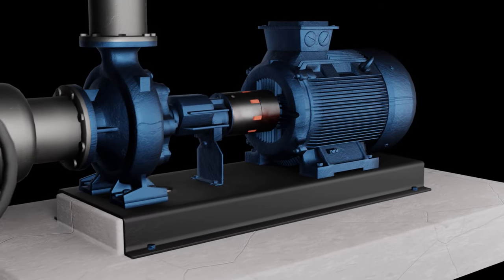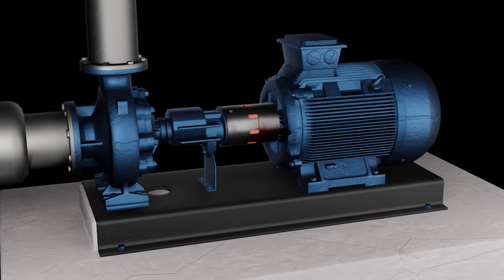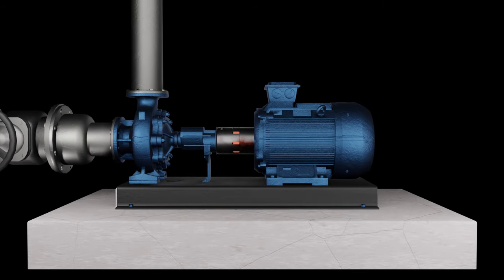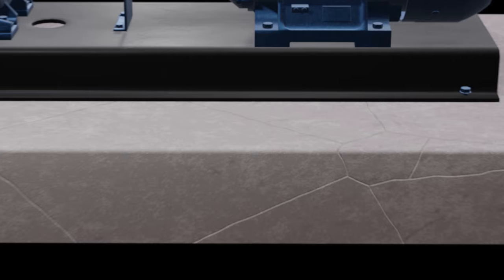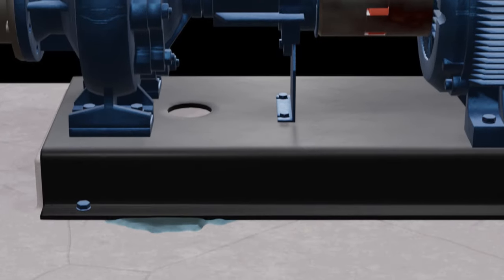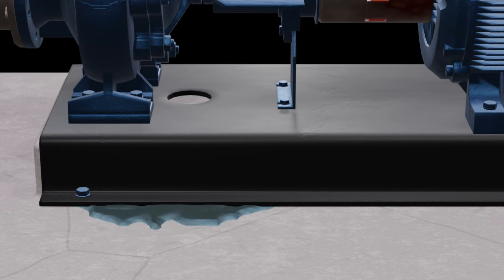They are used to support the machinery and its secondary parts, as well as a mass to minimize unwanted vibration. Begin by checking for cracked concrete bases or support columns and water seeping between the base plate and concrete foundation.